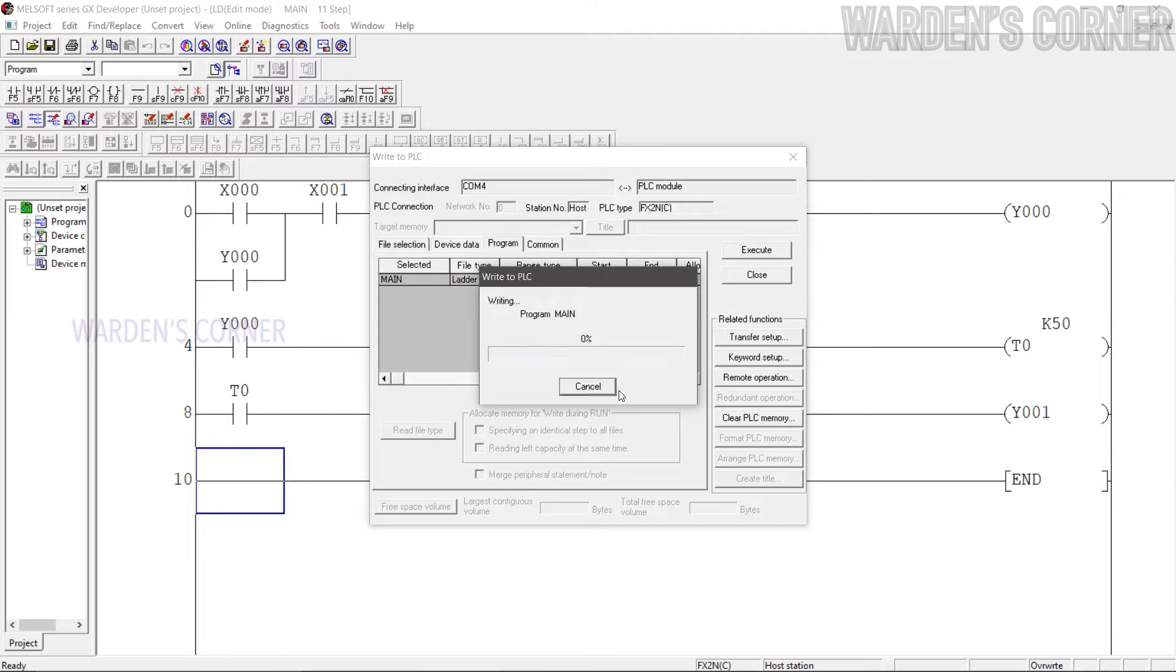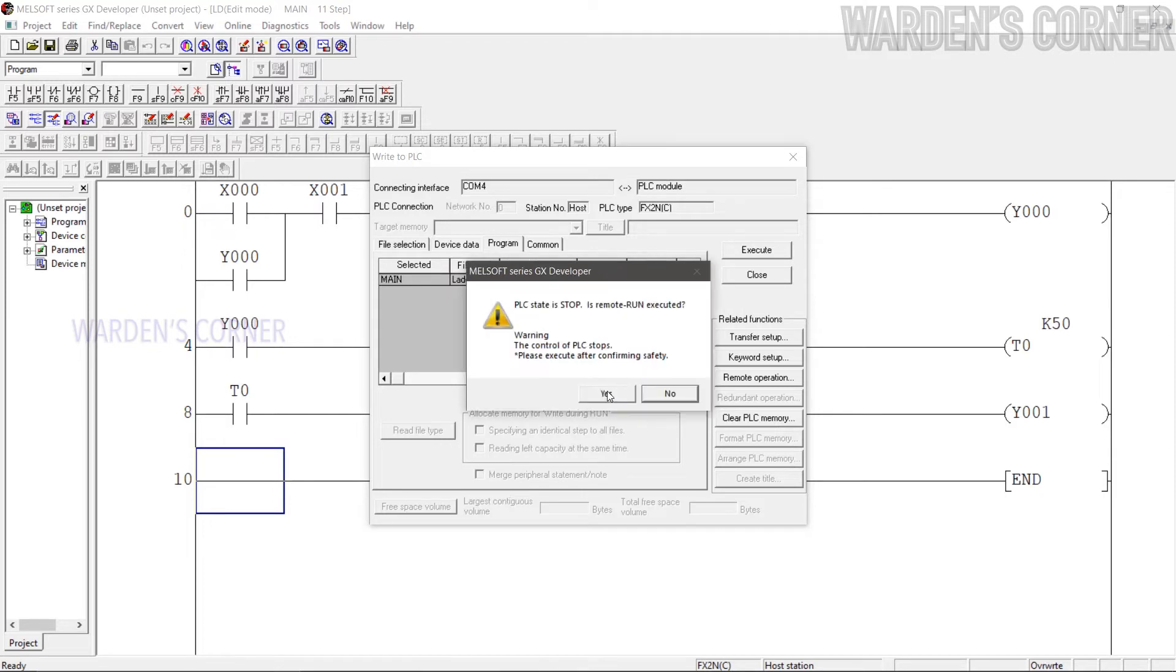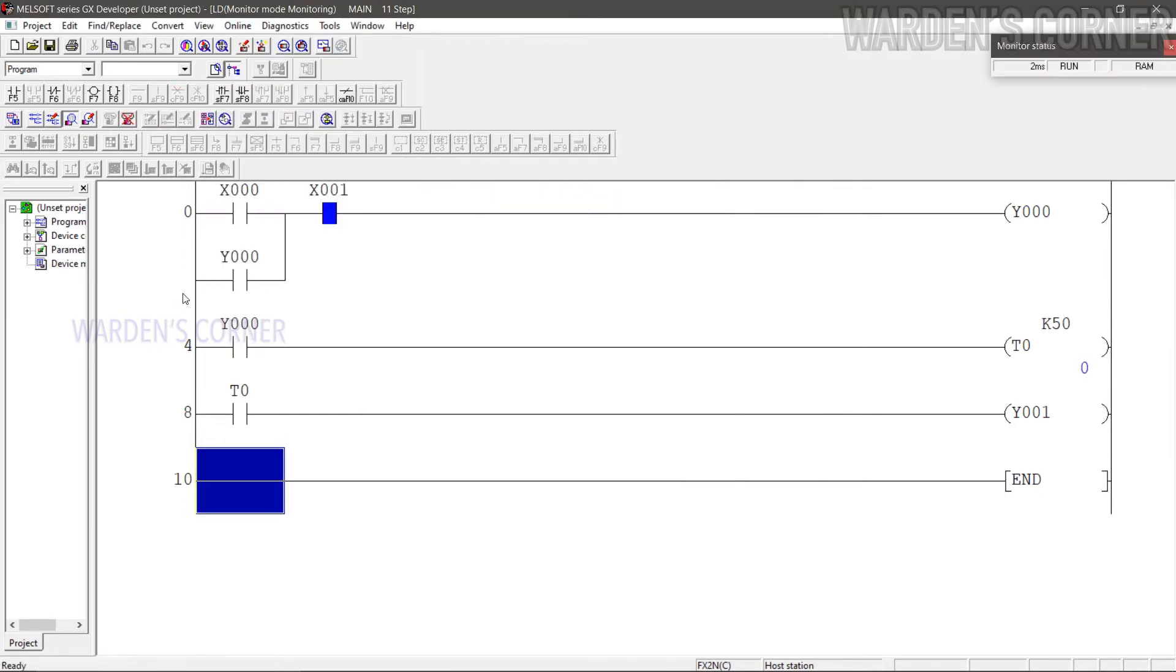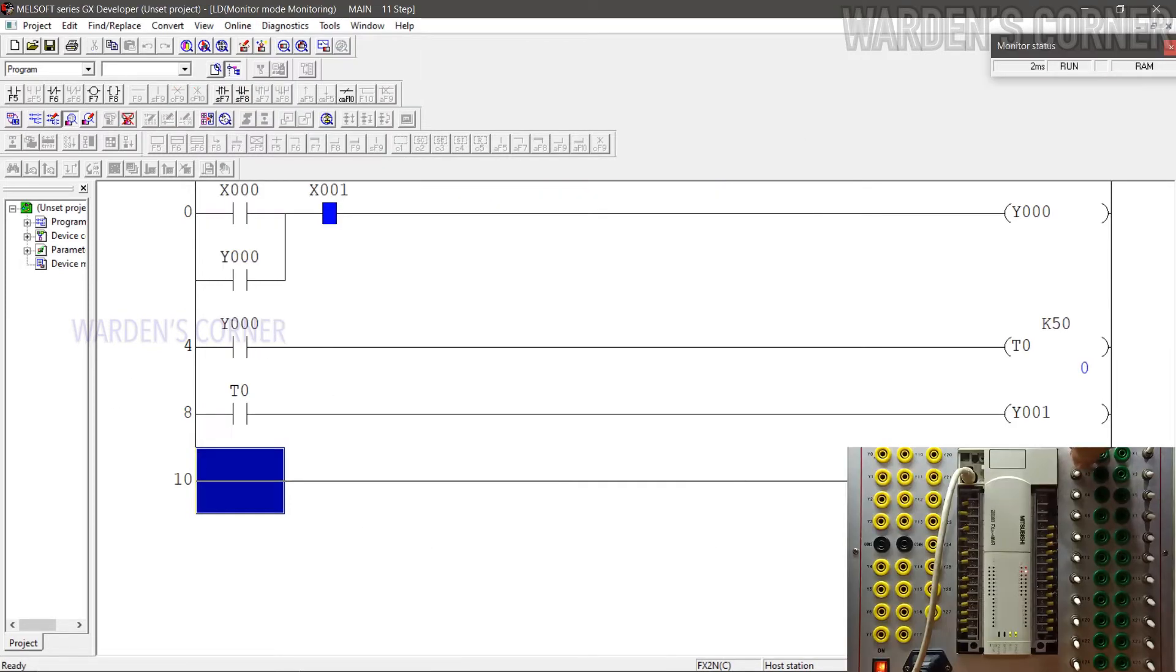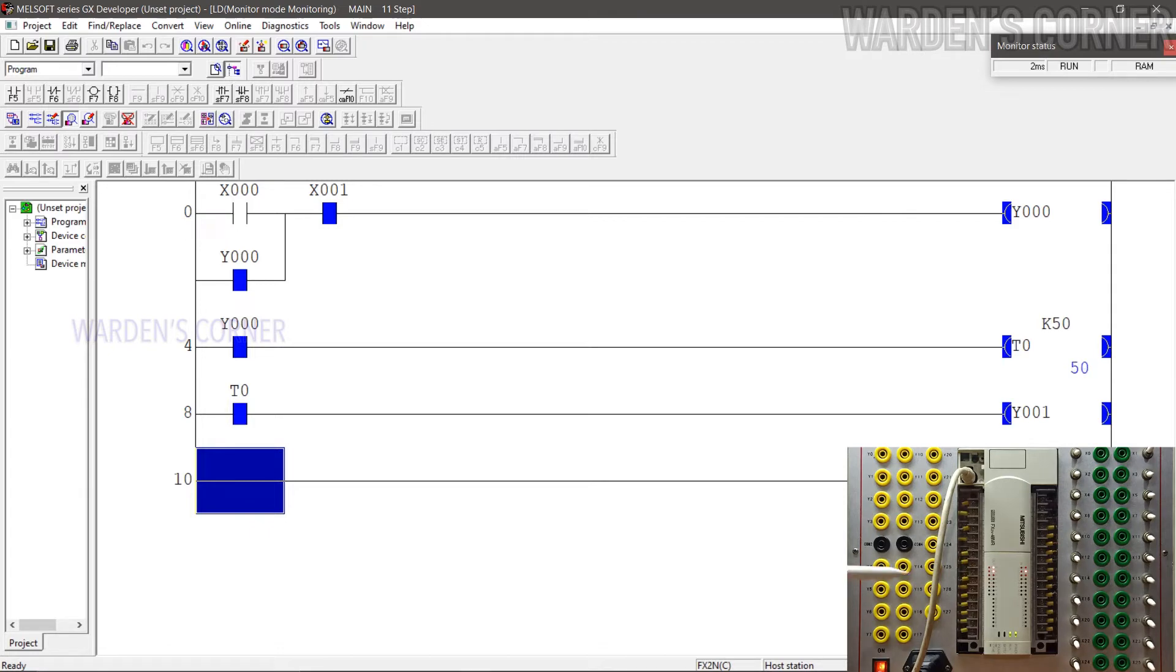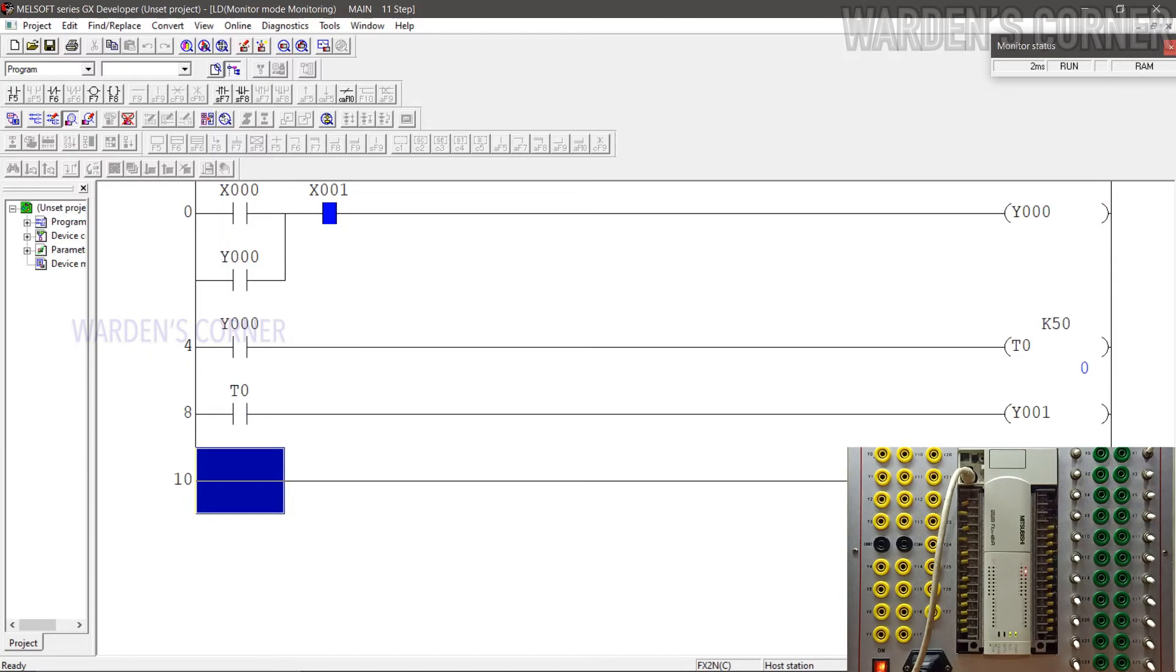To transfer the logic program to the PLC unit, just do the Convert to Monitoring Procedures and simulate the program. Press the Start button, Timer 0 Energized. When the timer accumulates 50 time value or 5 seconds, Y1 or the output will be activated. And press Stop button to deactivate the logic program.